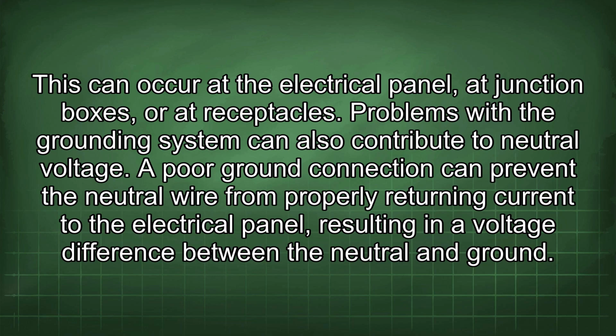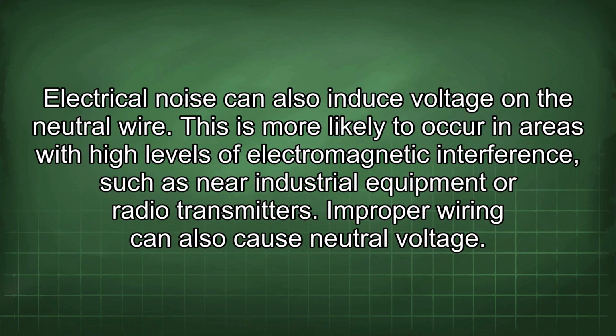Problems with the grounding system can also contribute to neutral voltage. A poor ground connection can prevent the neutral wire from properly returning current to the electrical panel, resulting in a voltage difference between the neutral and ground. Electrical noise can also induce voltage on the neutral wire.